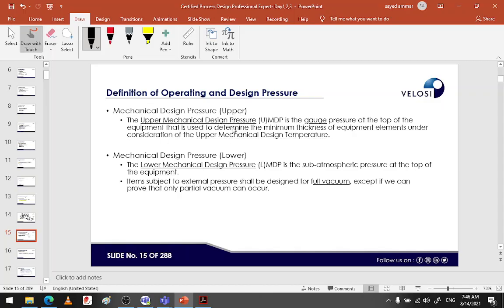We have one upper, we have one lower. The upper is the pressure at the top of the equipment that is used to determine the minimum thickness of equipment elements under consideration of the upper mechanical design temperature. When we define a mechanical design pressure, we have to tie it with the temperature. Why? Because as per ASME Section 8, the design pressure fluctuates with the temperature.